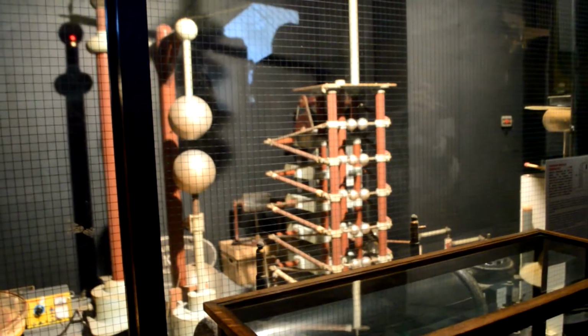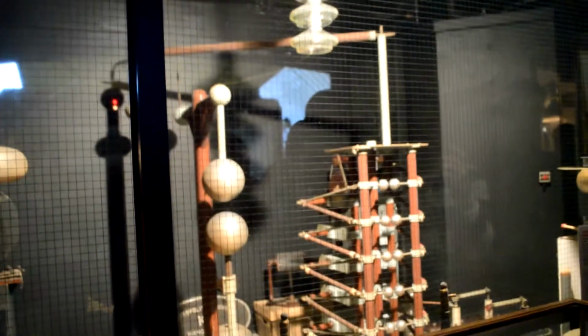Okay, so I'm going to attempt to operate the impulse generator now. It's a little bit fiddly because I've got some remote controls to get on with. Do we have a red light? Yes, we do. That's encouraging. Now I'm going to raise the voltage slowly from 0 to 40 kV. It may trigger itself, but if it doesn't, I've got a button to press. So it's a very short, sharp discharge up in the ceiling. Approaching maximum voltage now, charging voltage. There it goes. And I can let it do 4 more of those.